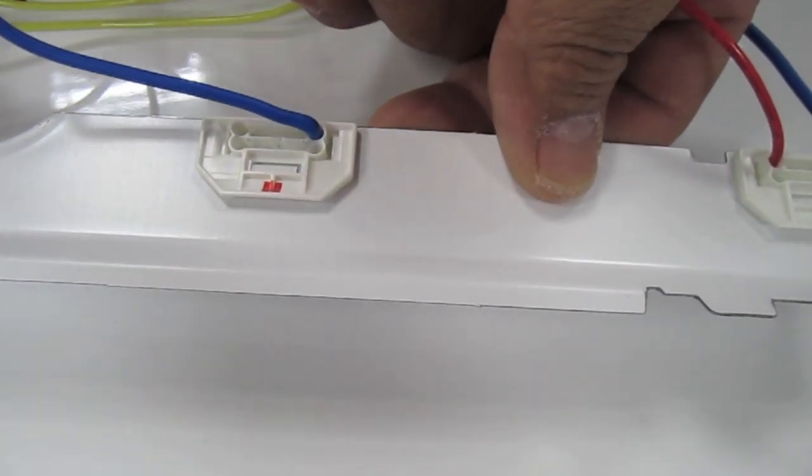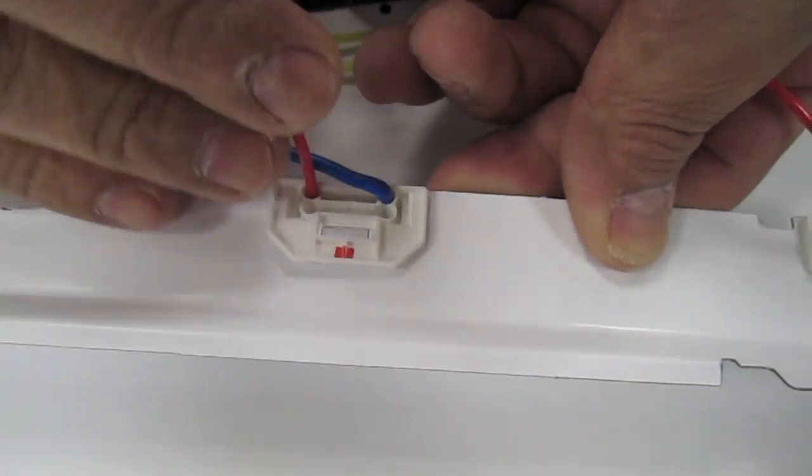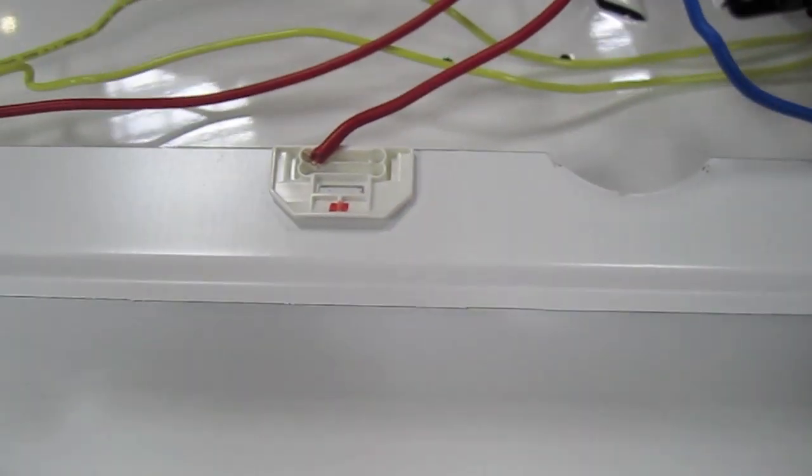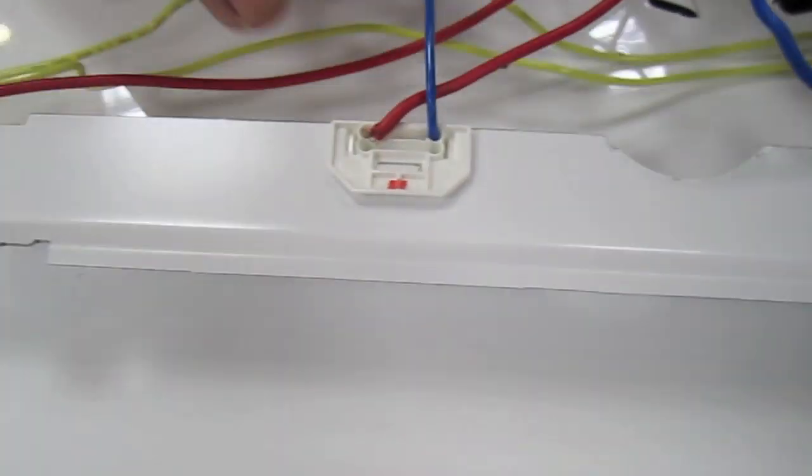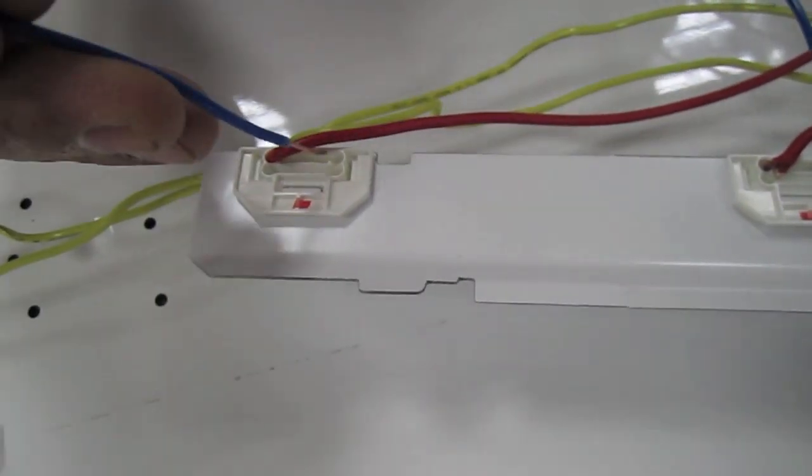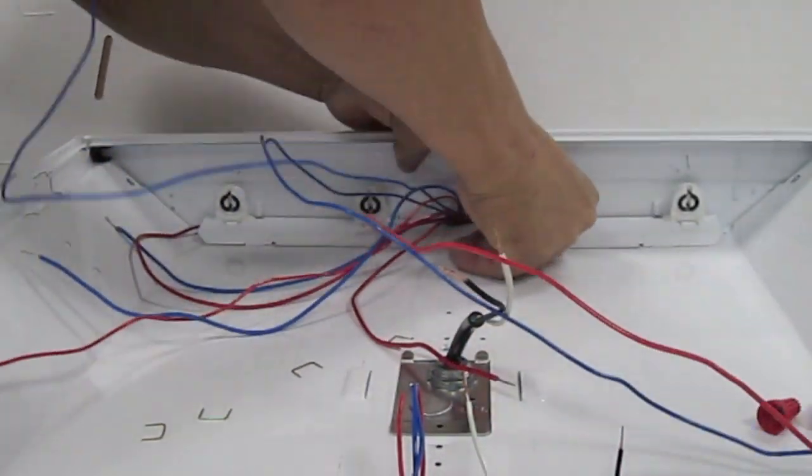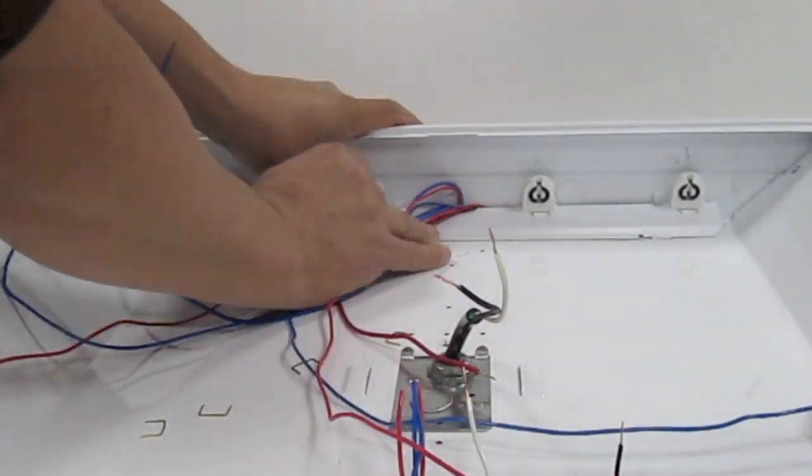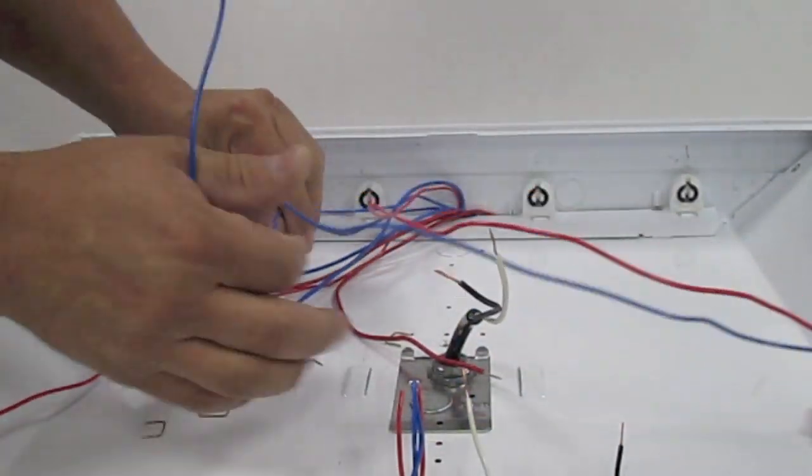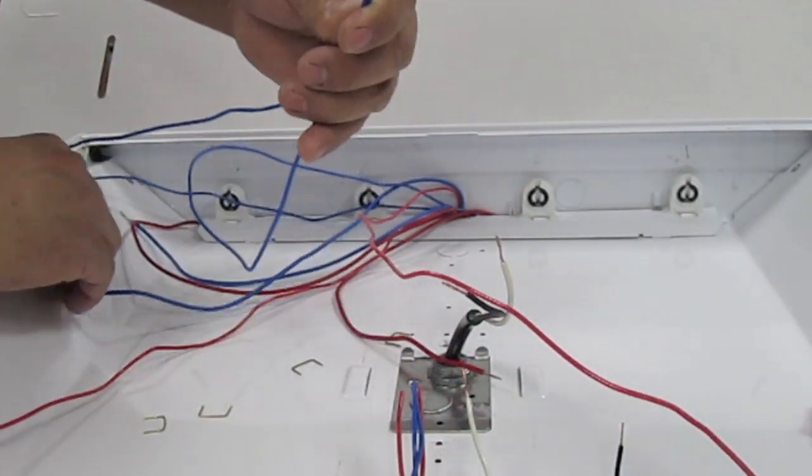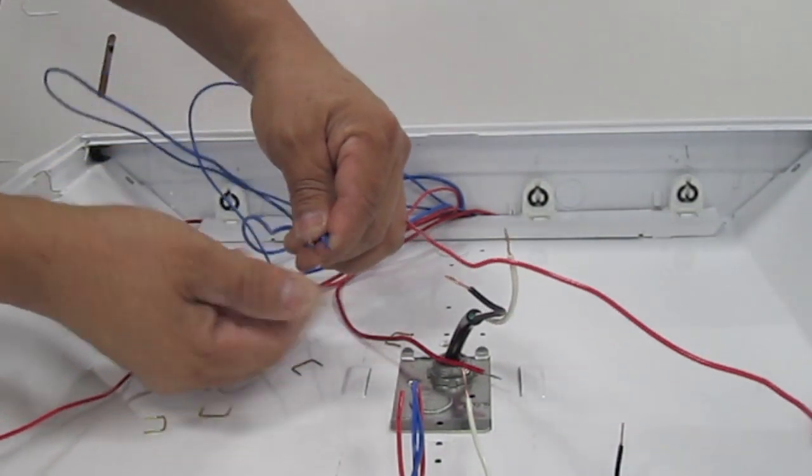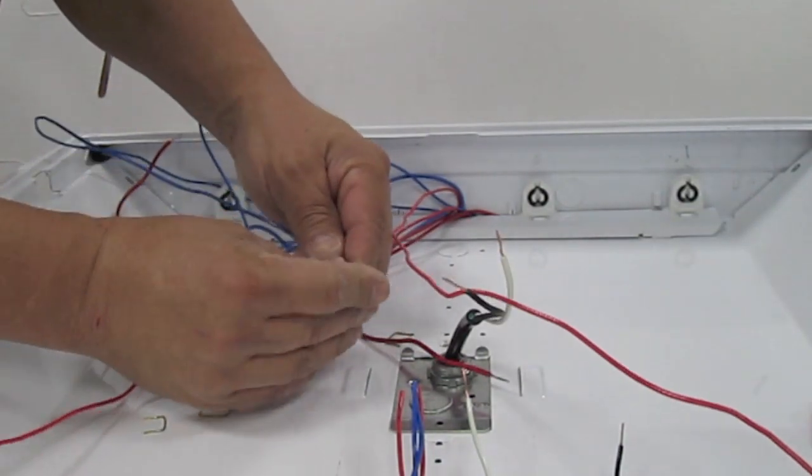Insert the new red and blue wires. Replace the lamp holder cover plate. Connect the blue wires to the white wire and connect the red wires to the black wire.